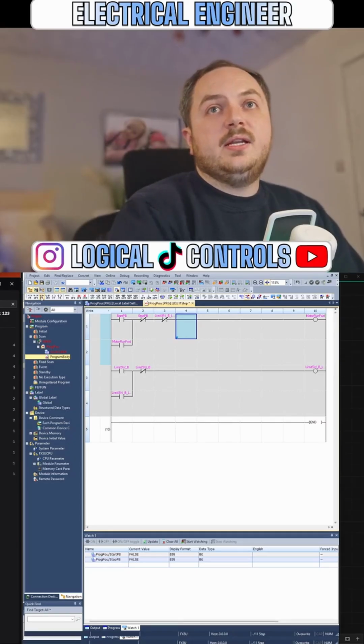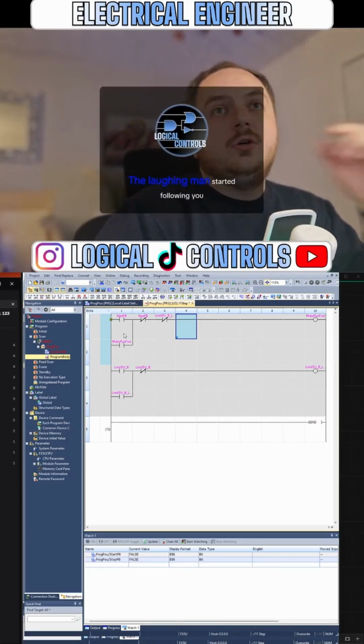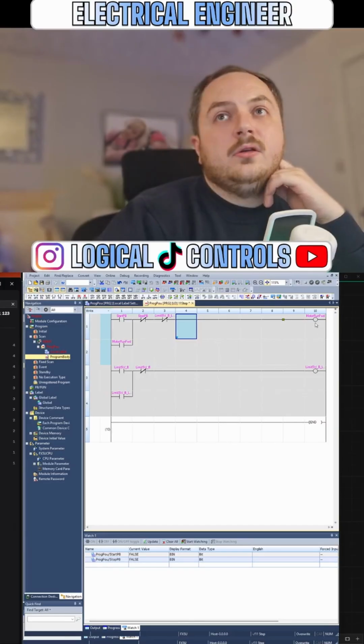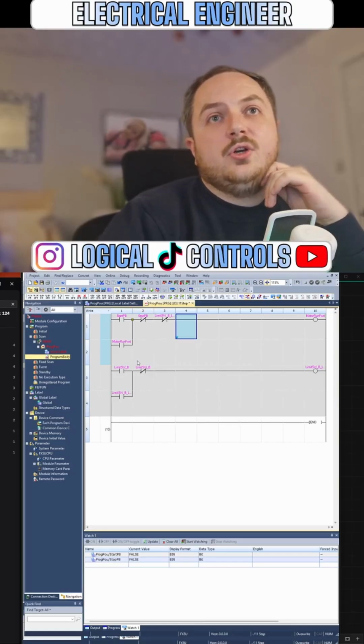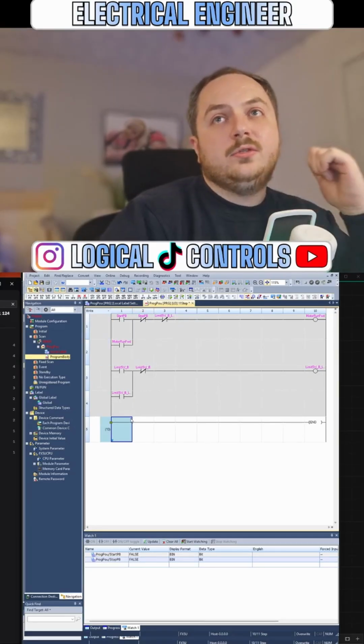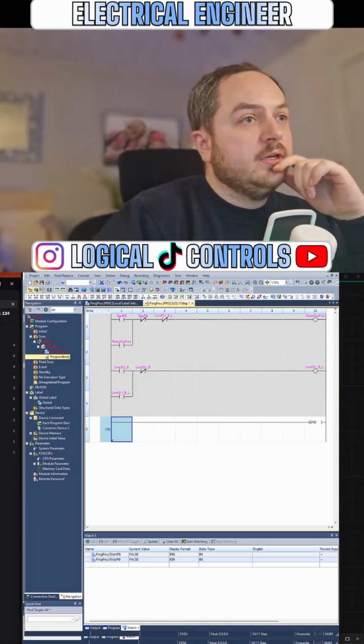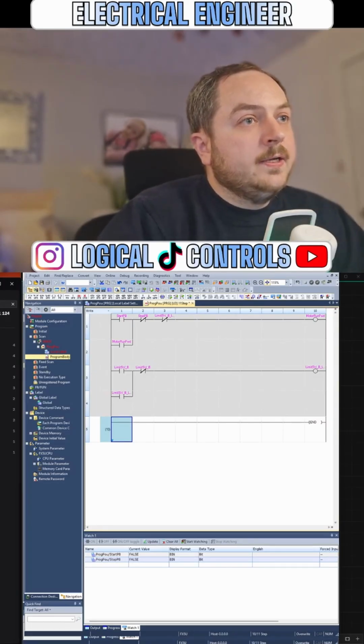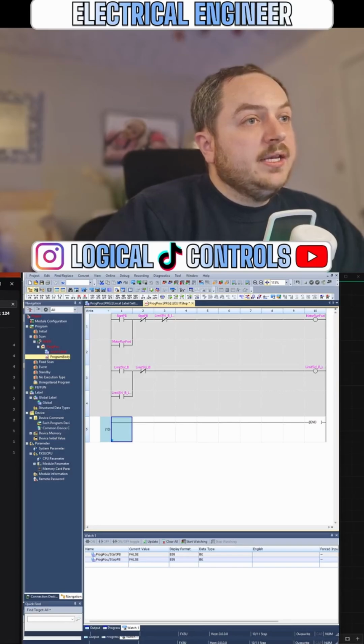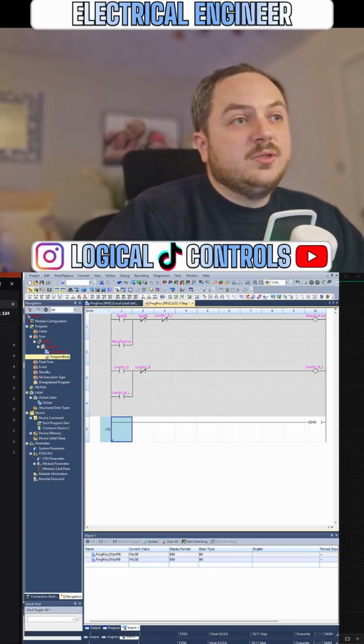Limit switch B latch. Press the start button, I'm going to run forward, keep running forward till we hit limit switch B. We'll latch that up, that's going to open that up, and then once that's open, we can go backwards. Let me find the comment again: motor goes A to B, hits limit switch B, goes back, hits limit switch A and stops.